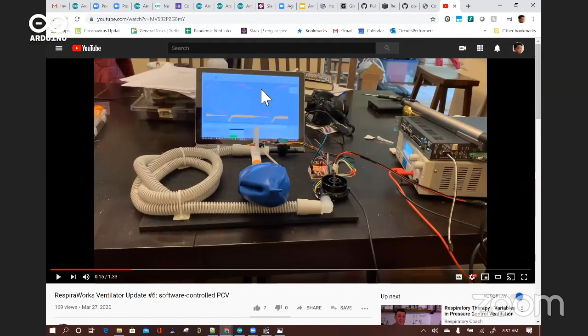Yeah. So we have a blower. I'll just let the video do the talking. We have a blower here, we have motor control, and the Arduino here controlling the closed loop breathing cycle. Our pressure sensor here is essentially a differential pressure across an orifice. This is our test lung that we're using to perform this test. And then there's also a patient pressure sensor here so that we can control both volume and pressure independently. Our initial focus is we're working with a hospital in Guatemala, Hospital Atlan, to provide them with ventilators there.